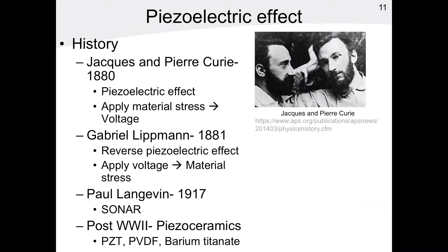How they work with ultrasound devices is, in transmit mode, we use the reverse piezoelectric effect. We apply a voltage across the faces of the ultrasound transducer, and the stress in the material is manifested as a displacement, as is shown with this graphic. When the ultrasound is in receive mode, we use the piezoelectric effect. So the returning pressure waves place stress on the transducer, causing a small displacement, which is then converted into an electrical signal.